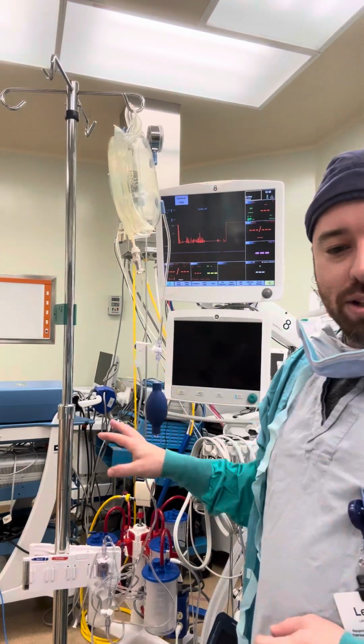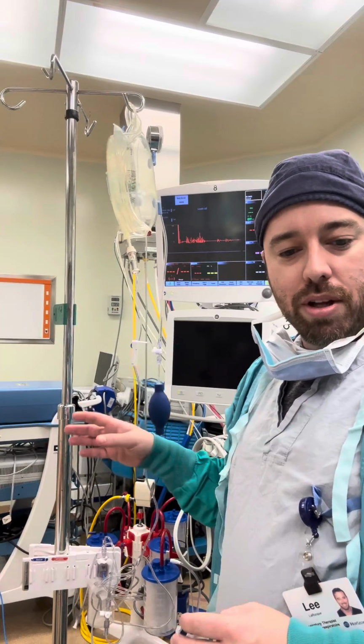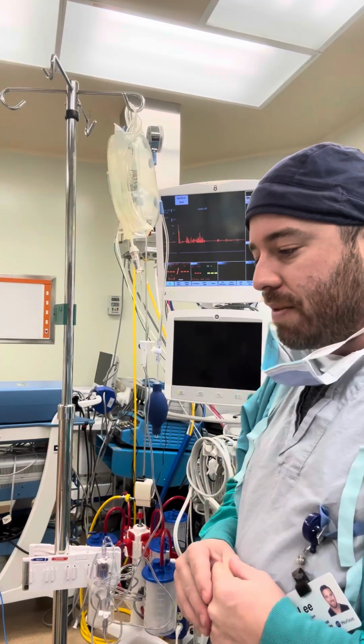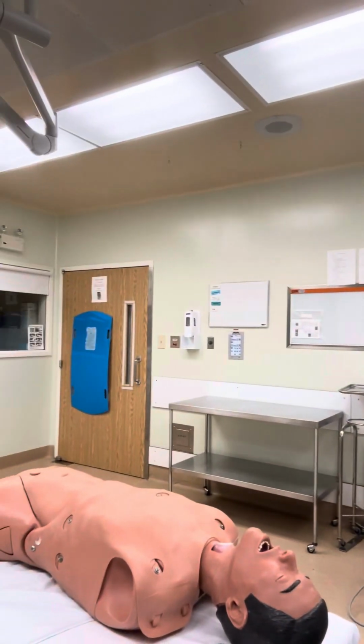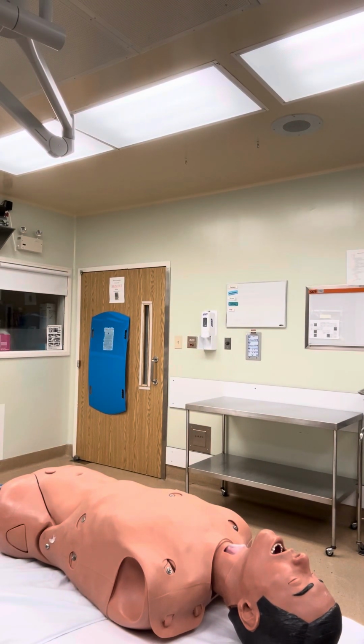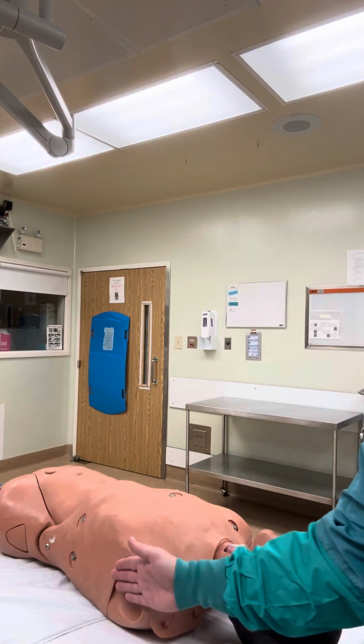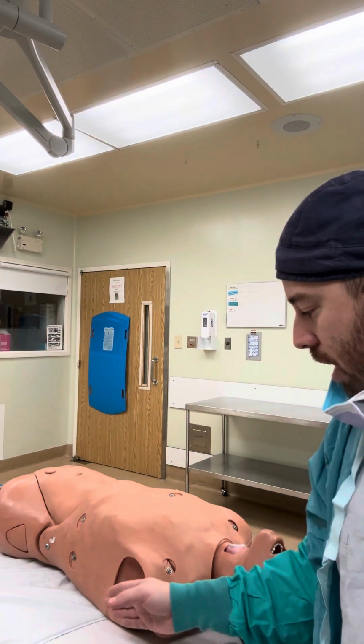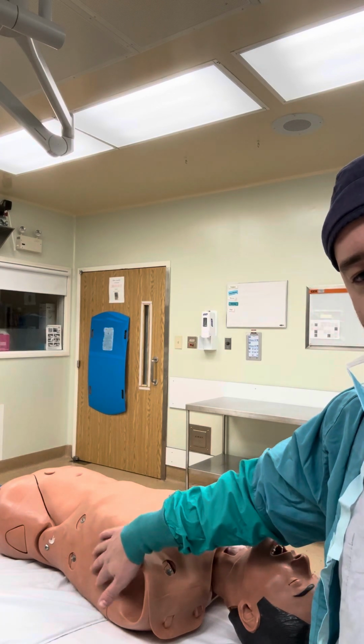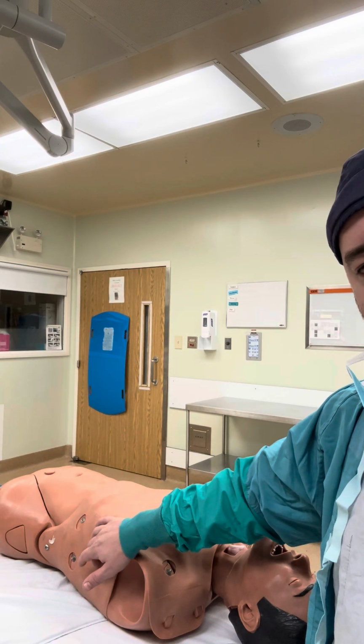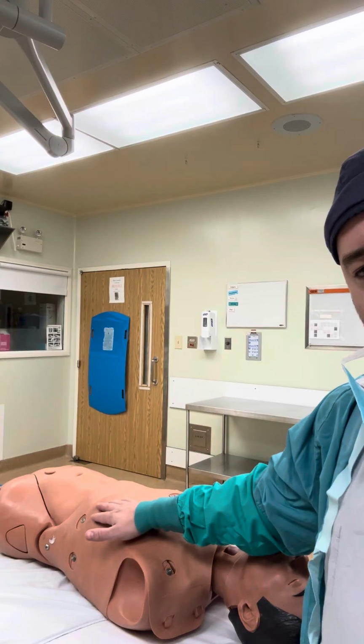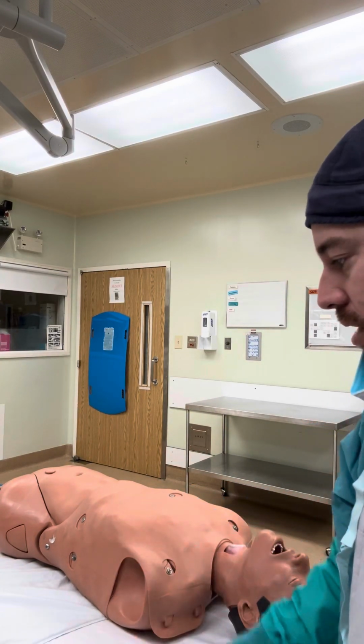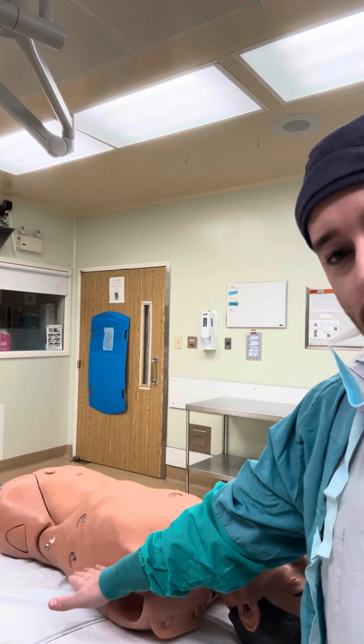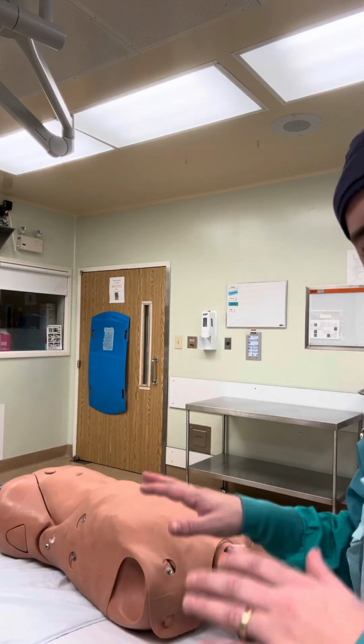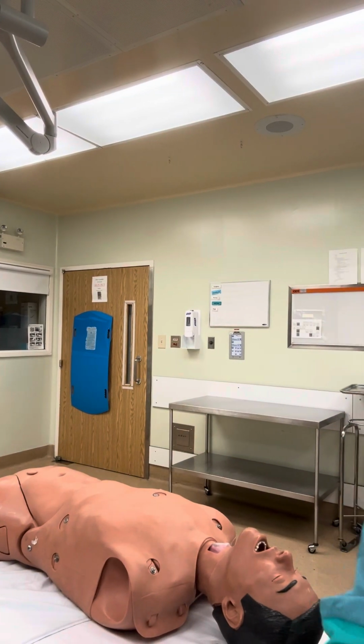Now that we've primed that system and double checked to make sure that there are no bubbles, the other thing we want to do is zero that for the patient. When we're zeroing for the patient, as you can see my patient's located here, we want to make sure that the transducer is set at the proper level, which is known as the phlebostatic axis. The phlebostatic axis is found between the fourth intercostal space and about halfway through the anterior posterior diameter of the chest. So I want to make sure that that's zeroed, and if the table goes up and down, to adjust that as needed.